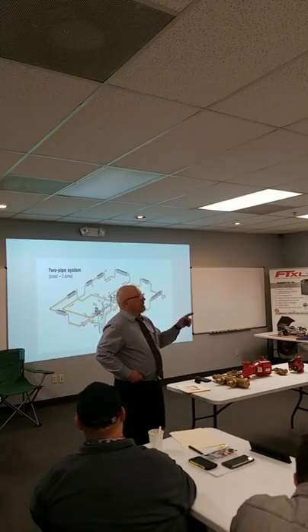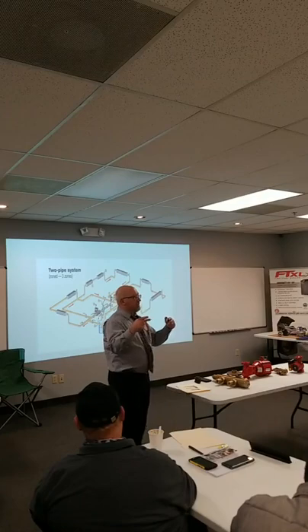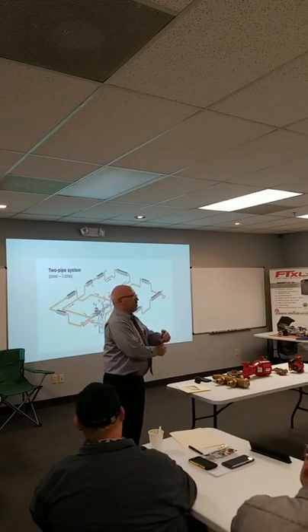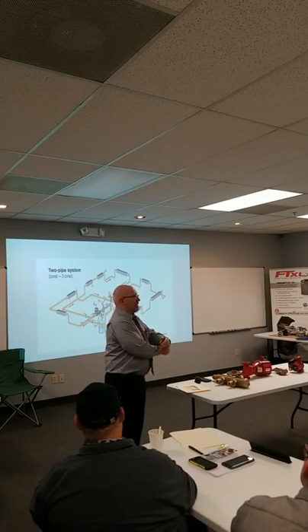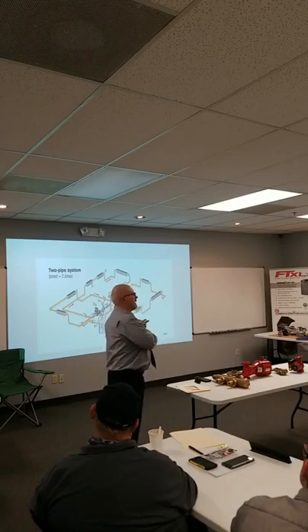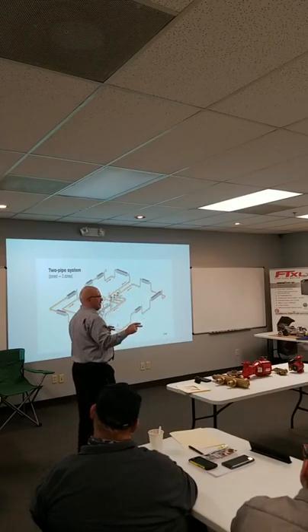Expansion tank. You could, but remember now the differential of the pump, the outlet of that pump, is adding pressure. So what if your boiler has a 30-pound relief and you've got 20 pounds in the system and you turn that pump on? You could pop relief valves. And you're saying, why am I popping a relief valve every time the pump turns on? Because you're adding that pressure to the system. So just be aware of it, but you're right.